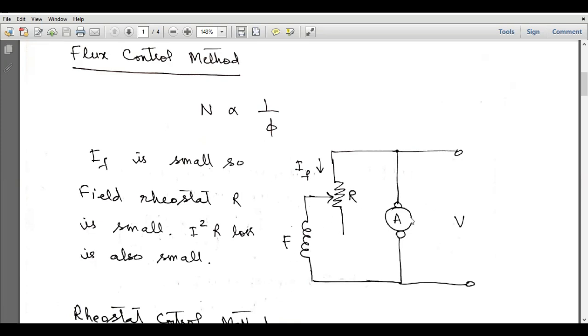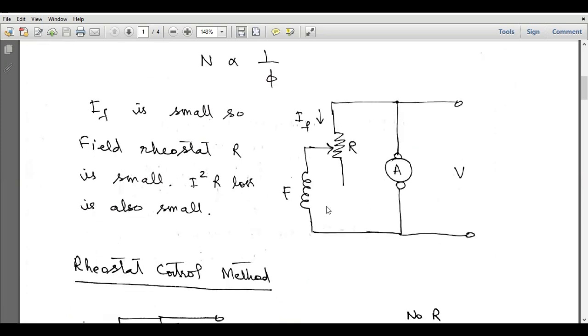This is a shunt wound DC motor. The field rheostat resistance is small, so the I²R loss is also small. In DC shunt motors, this method is favorable because the field current is normally small, so the I²R loss across the resistor is small. When we increase the resistance, field current decreases and speed increases; when we decrease the resistance, field current increases and speed decreases.